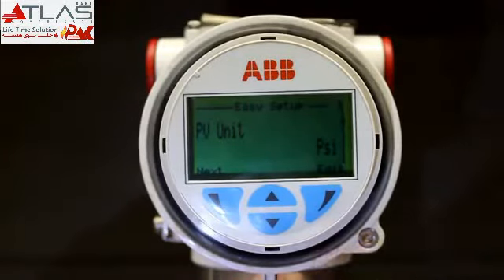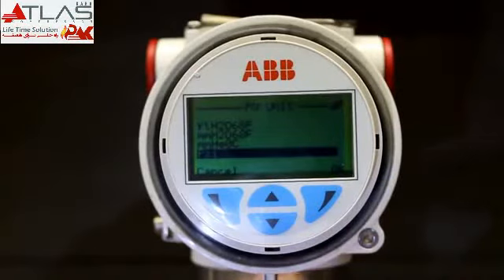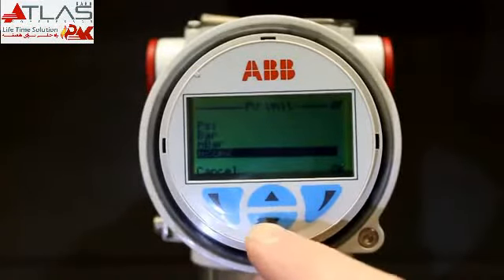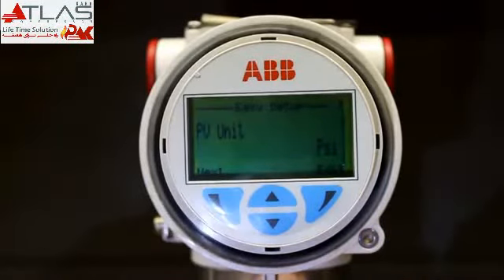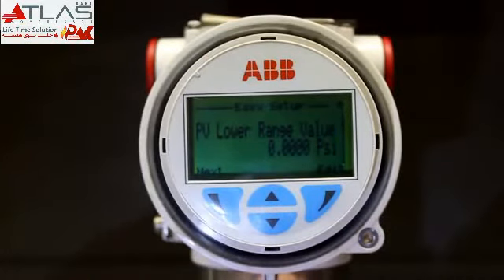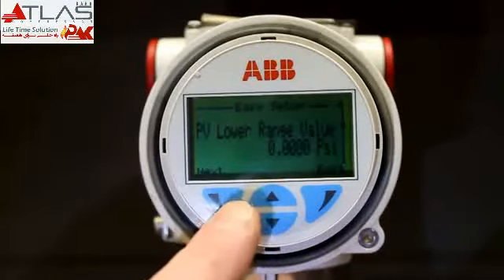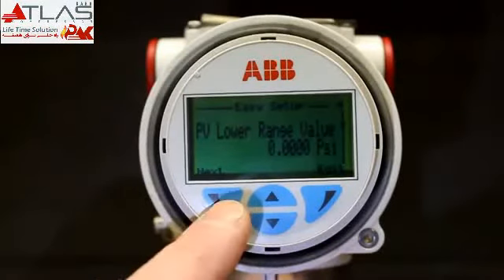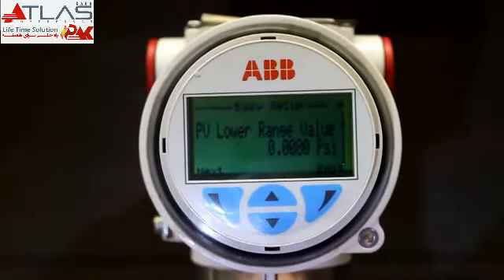We'll hit next to go to the next option in easy setup, which is primary variable unit, and in this case it's PSI. Again, if you want to change it, you hit edit and you get all your menu options here. You can hit OK when you find the one you want, or you can hit cancel to X out and go back to the previous menu option. So we'll hit next again, and here we've got primary variable lower range value. You can change it, but normally we keep things at 0 for low range value.